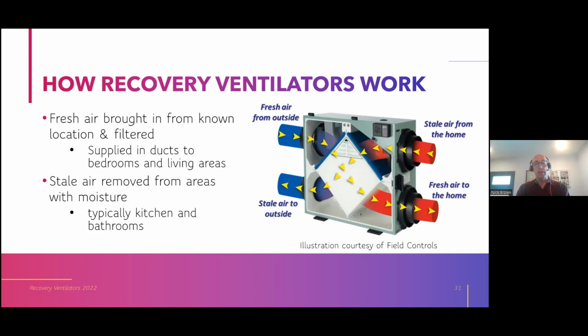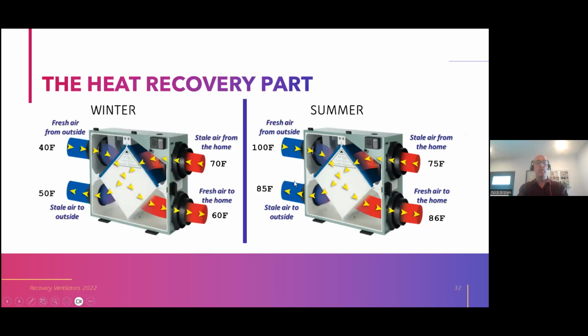And then the stale air is coming in the upper right in the box here and swapping heat with that stream. So let's look at the heat recovery part, and maybe these numbers will help illustrate the concept. In winter, let's say we've got a 40-degree day. We're bringing in that 40-degree air. In an exhaust-only scenario, that would be a burden on our heater, right? We're bringing in all that air at 40. Our house is, let's say, 70, the return air, this stale air.